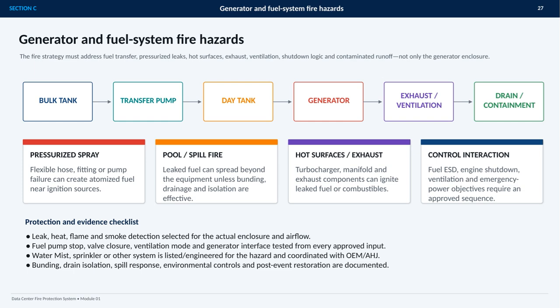Leaked fuel may travel beyond the equipment unless bunding, drainage, and isolation are effective. We also need to account for turbochargers, manifolds, exhaust components, ventilation, and other hot surfaces that can ignite fuel or nearby combustibles. Finally, control interaction matters. Fuel emergency shutdown, engine shutdown, valve closure, ventilation, and emergency power objectives must operate in an approved sequence.